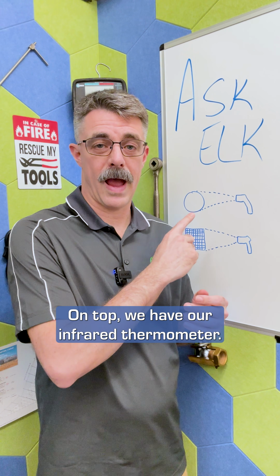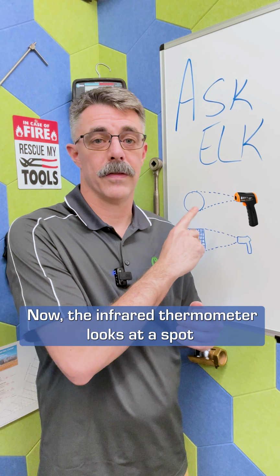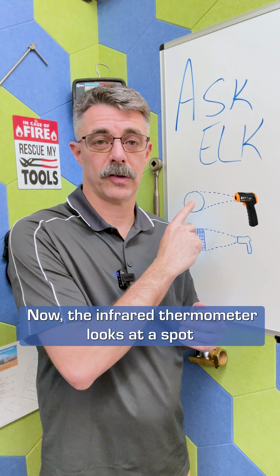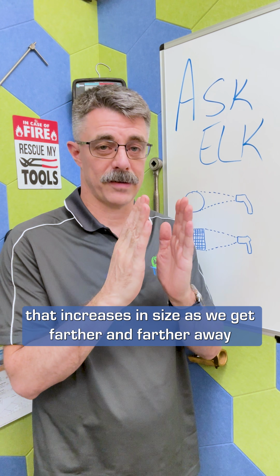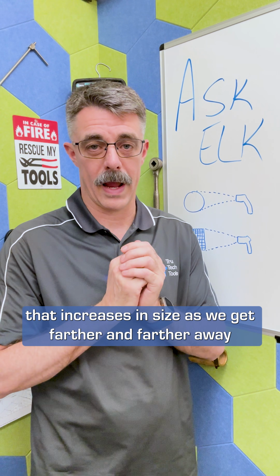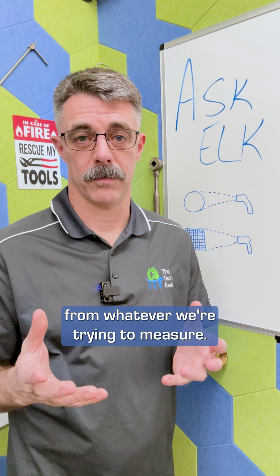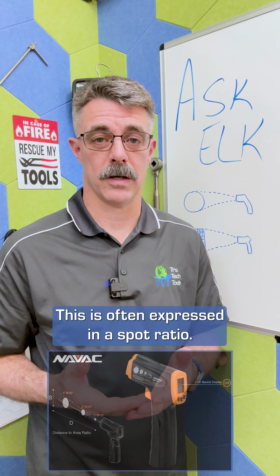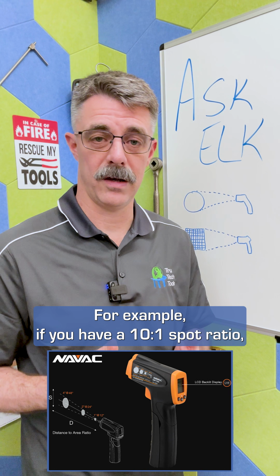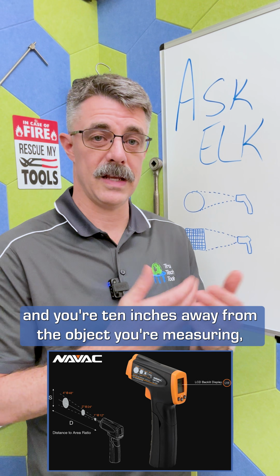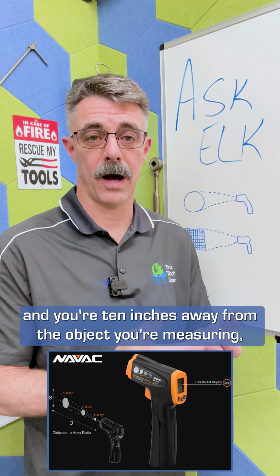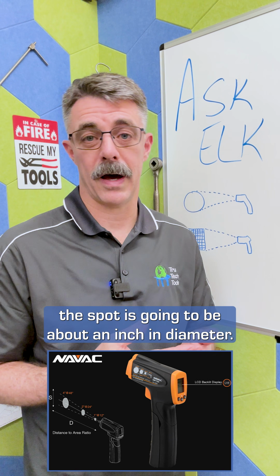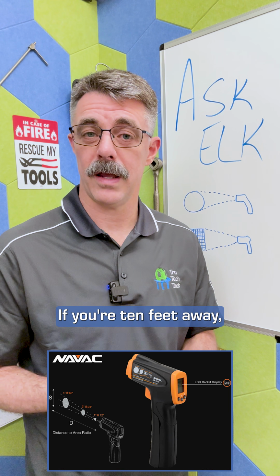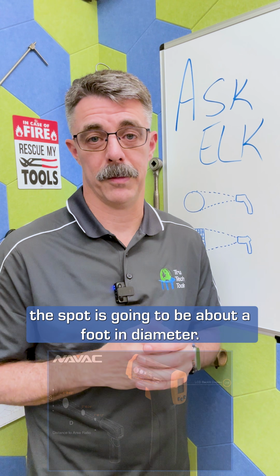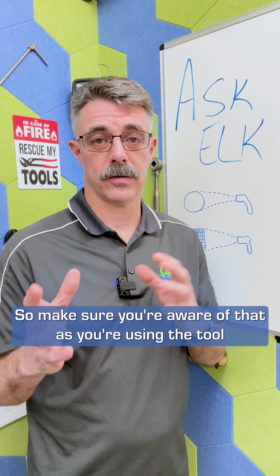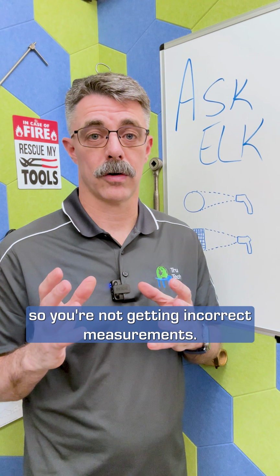On top, we have our infrared thermometer. Now, the infrared thermometer looks at a spot that increases in size as we get farther and farther away from whatever we're trying to measure. This is often expressed in a spot ratio. For example, if you have a 10-to-1 spot ratio and you're 10 inches away from the object you're measuring, the spot is going to be about an inch in diameter. If you're 10 feet away, the spot's going to be about a foot in diameter. So make sure you're aware of that as you're using the tool so you're not getting incorrect measurements.